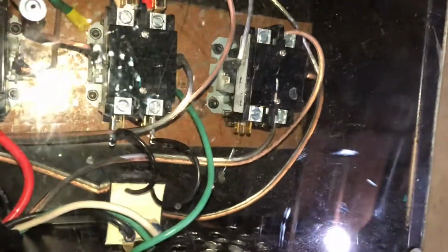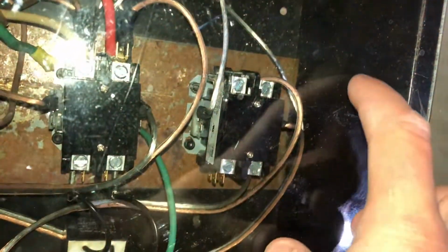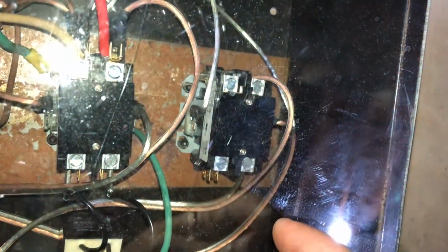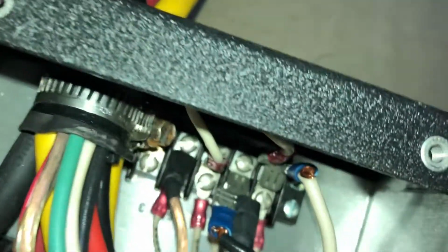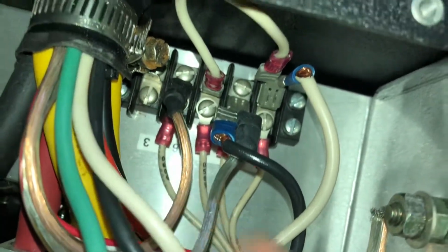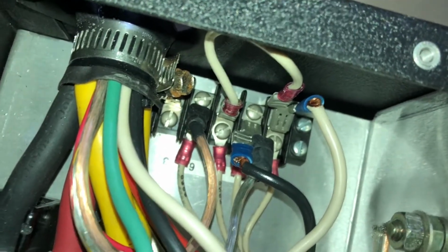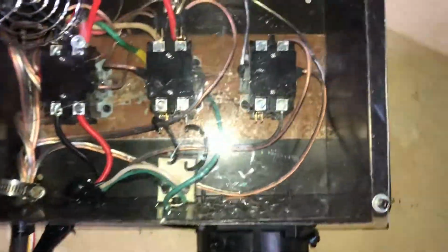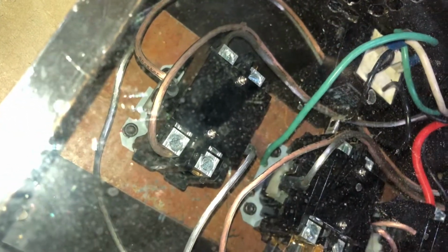And this last contactor actually doesn't have any power going to it per se, but all it does is close those two contacts. So when that contactor closes, it short circuits these two wires, which, if you remember me saying before, pins 4 and 6, when they're connected together, actually switch on the 120 amps going to the lamp. So all that's doing is, oh geez, a lot of glare. All that's doing is just short circuiting those two wires to switch on the high current going to the lamp.